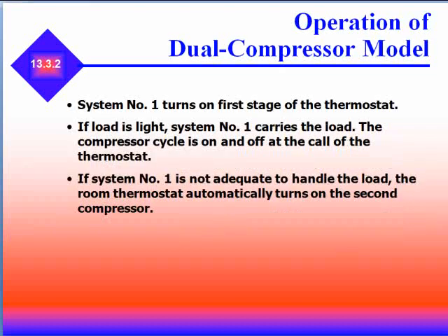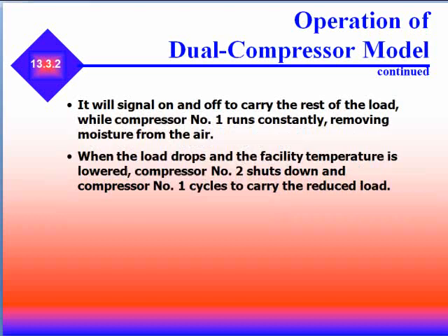The operation sequence works as follows: system number one turns on at the first-stage thermostat. If the load is light, system one carries the entire load, with the compressor cycling on and off at the call of the thermostat. If system number one is not adequate to handle the load, the room thermostat automatically turns on a second compressor. It will signal on and off to carry the rest of the load while compressor number one runs constantly, removing moisture from the air.